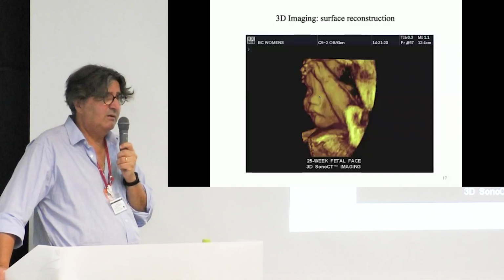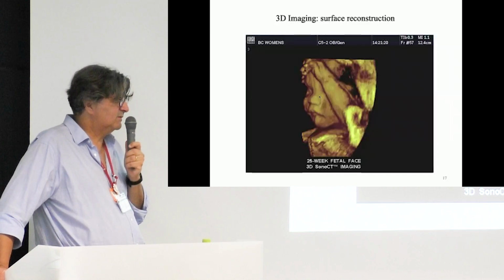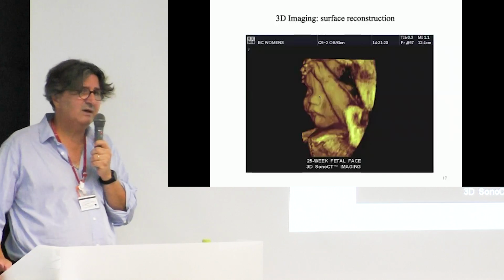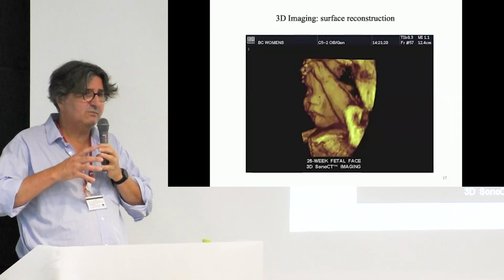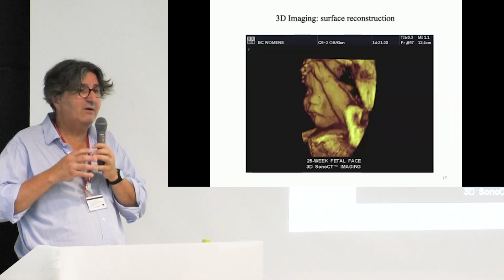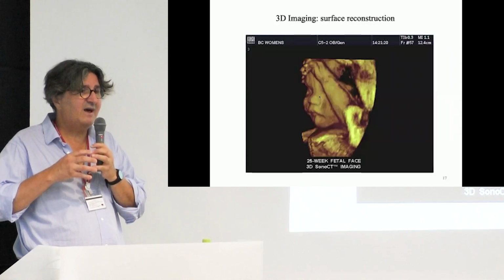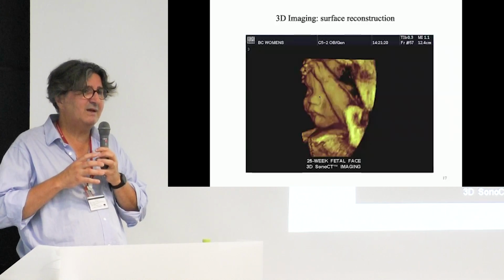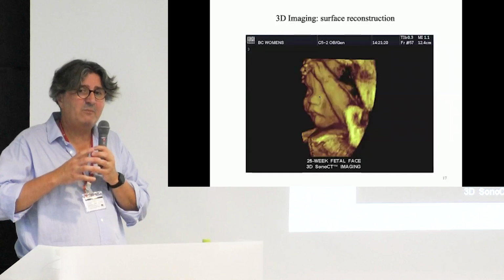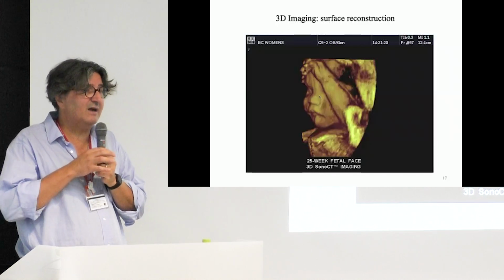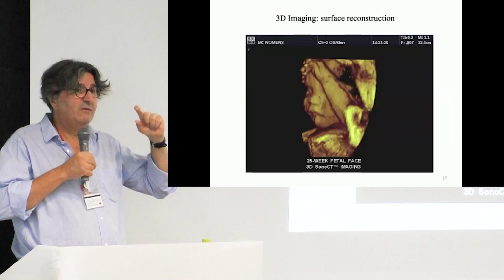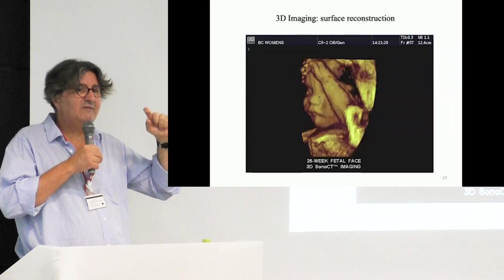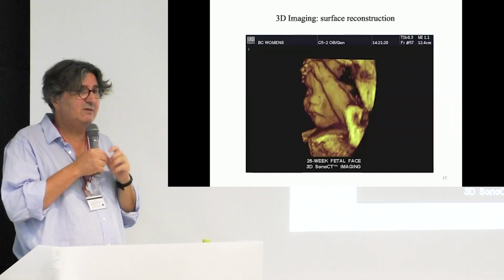So how do you manage all the connections? This is why today matrix transducers are used, but up to now they had a lower resolution than array transducers, because the number of elements that you have compared to the image size, like the number of pixels on your camera, is relatively low to produce these 3D images.